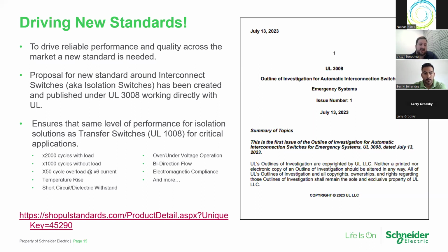And the idea behind it is that if you have transfer switches with generators for backup power, that an interconnect device, which basically enables an inverter to provide backup power, should not be any less robust or any less reliable than what we expect out of a transfer switch and generator. So obviously you can see the inspiration between the two, UL 1008, UL 3008, they're parallels there. And a lot of the testing standards around the two do mirror each other. But there are advances. The standard covers things like short circuit performance, endurance performance, overload performance, temperature rise, all those things, just like transfer switch UL 1008.